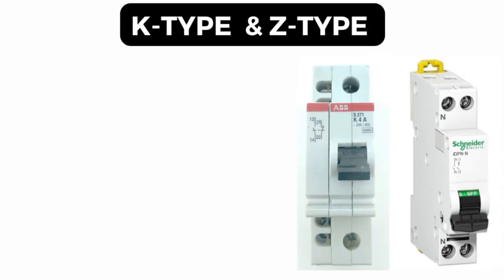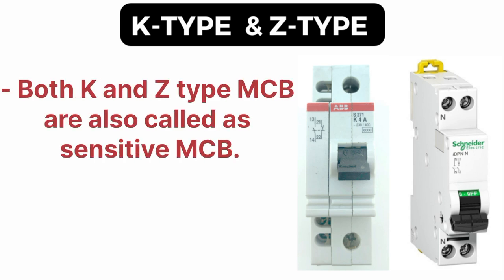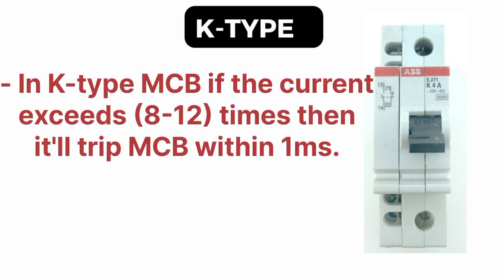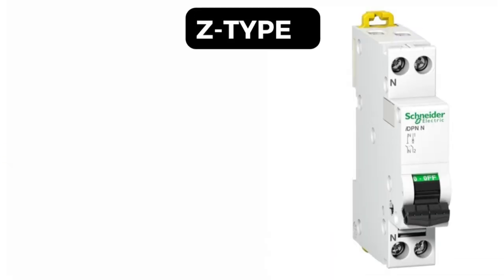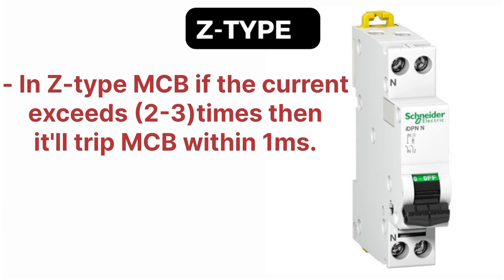K type and Z type MCBs are also called sensitive type MCBs, because if the current exceeds even a little bit, it will trip the MCB suddenly. For K type MCB, if the current exceeds 8 to 12 times the rating, it will trip within 1 millisecond. For Z type MCB, if the current exceeds 2 to 3 times, it will also trip within 1 millisecond.